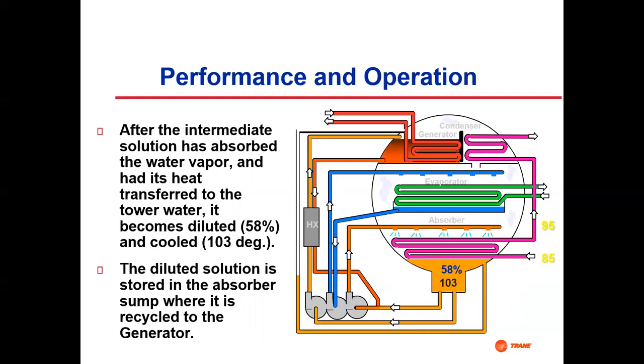Got some temperatures. We added one. We're at 103 down here. Cooling water, 85 in, 95 out here. Now, what we're going to see is that the cooling tower load is larger. For the same cooling load, we're going to have a larger cooling tower for this. So let me talk a little bit about cooling towers, because we're going to have a module in the course on cooling towers.